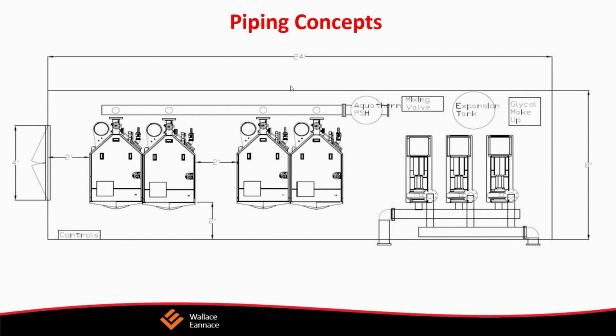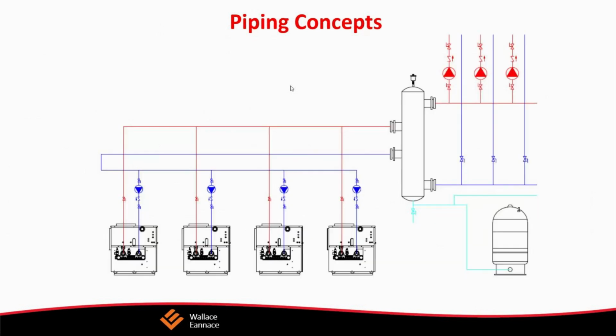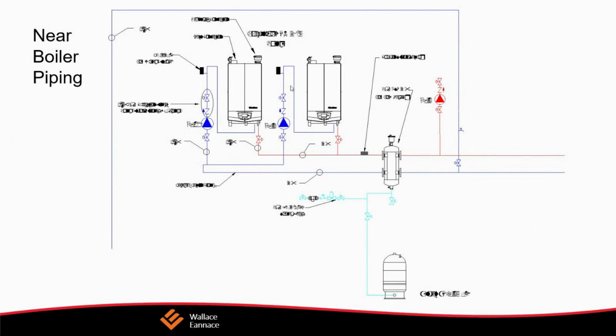They come in a variety of sizes. They can be pretty large or they can be small. The smallest one I think we make is 30 gallons. They're made by Lochinvar. You can connect them directly and use them in lieu of the primary secondary header, and it's a really good way of getting rid of applications where you run the risk of having zones that are very small, especially in radiant heat, that can be constantly calling for heat and short cycling the boiler.